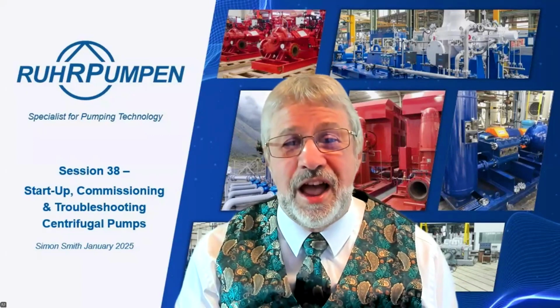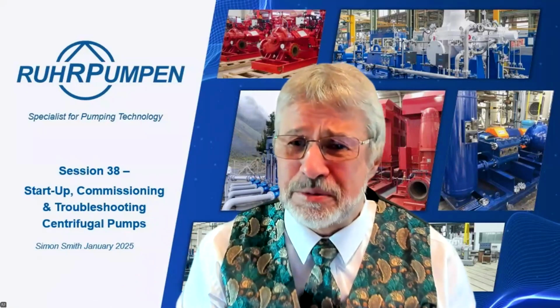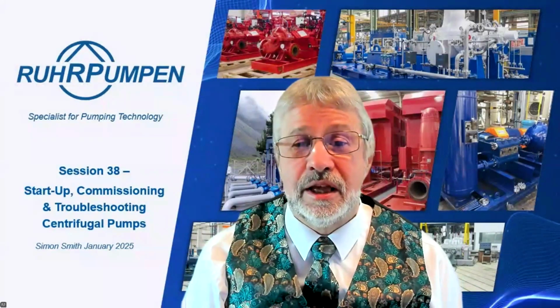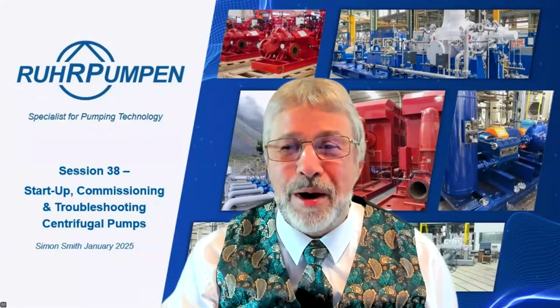You have to answer it case by case. If the pump rated flow is 20% higher than expected flow, and your point is to the right of best efficiency point, that'll be ideal, because once you've got 20% off that, you'll be just to the left of best efficiency point, perhaps. But what you want to avoid is oversizing a pump such that you're running well back to the left. If your pump's too large, you need a smaller pump.